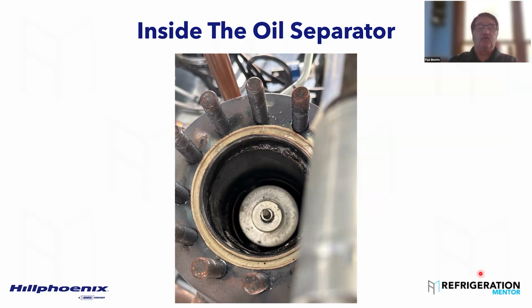So now I need to find out what's wrong with my bypass valve. It turned out that the bypass valve, somehow the gear stripped out in the bottom and it quit manipulating the valve. Fortunately, they had a bypass around the bypass. We were able to open that up and then get the rack back up and running. And I think he also had to add an extra gauge line from the vessel to the suction line because it was summer and he needed to get more pressure out of there. But we got it running. He ordered a valve, took the valve apart, replaced all the guts, put the valve back together, and off we went.